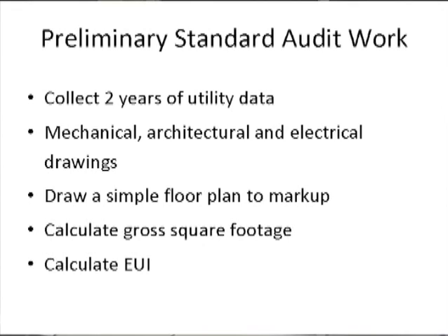That's something we run into a lot at UCF, is that we're constantly moving people out of one area and into another area, and what they do actually changes, and their density of people changes, and so equipment changes need to take place, but they don't always take place at the right time or the right way. And so we end up finding a lot of those things when we go out in the building, and some of those are really energy intensive type things. We find out the equipment is way oversized for the heat load that's there now, or vice versa.